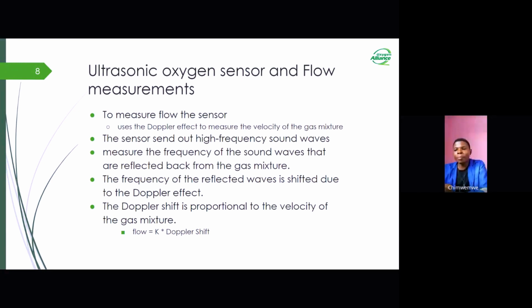By doing this, it can analyze the changes in frequency between the waves. So the sensor can then calculate the speed of the gas. With additional information about the cross-section area, it can give the volumetric flow rate of the gas. This can be shown on the oxygen analyzer, which is using this type of sensor.